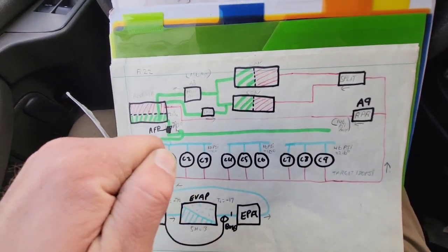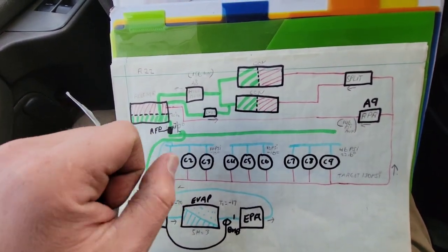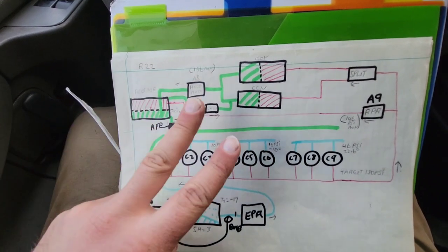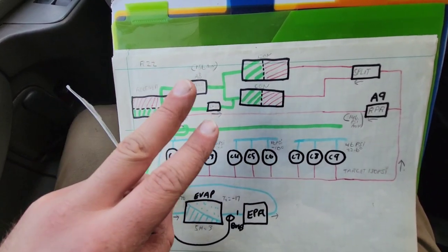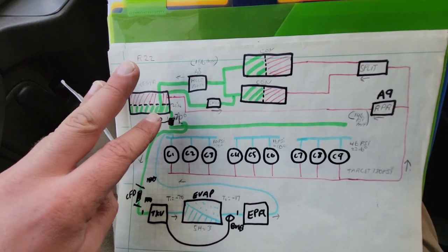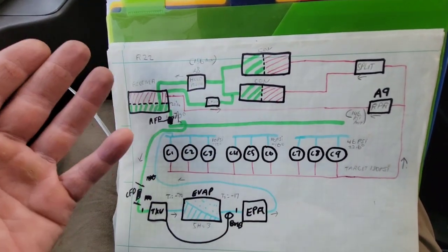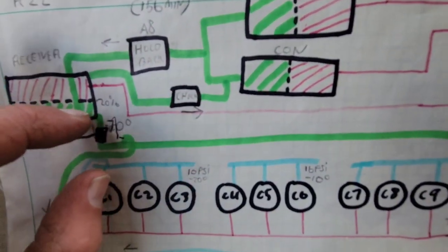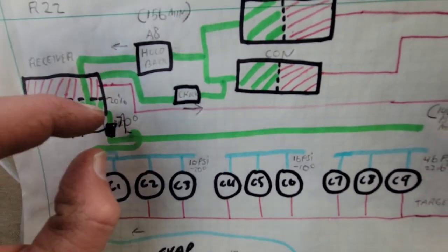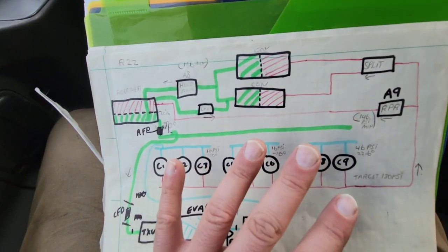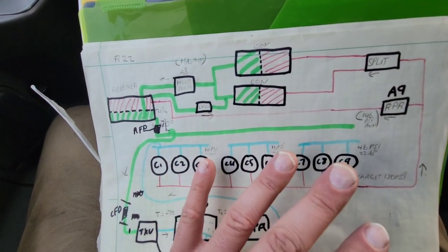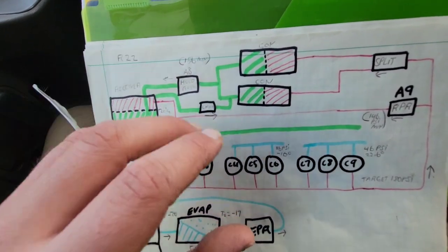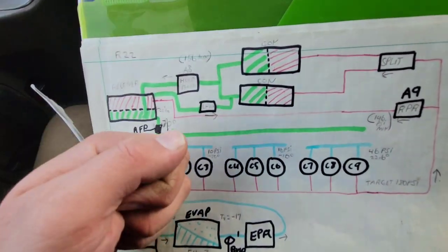But let's say your receiver level is 20% or 50%, but your sight glass is still flashing. Then it's very possible that it could be your rack filter dryer. That's why those are the next three steps. That's a telltale sign that it's your rack filter dryer, and it's restricting flow.